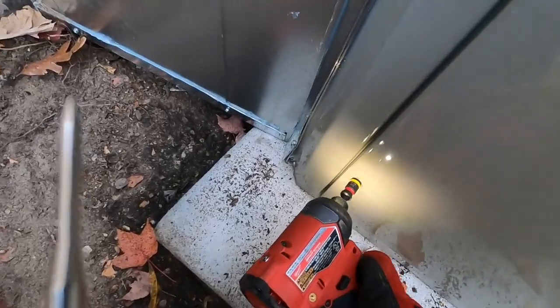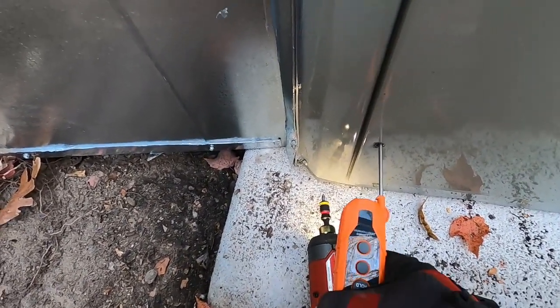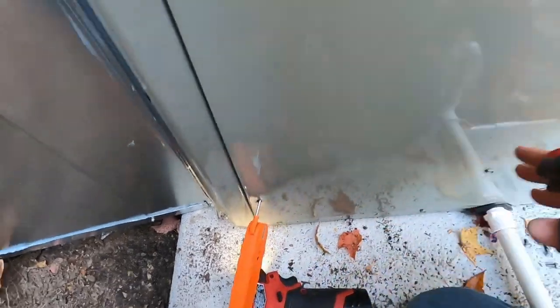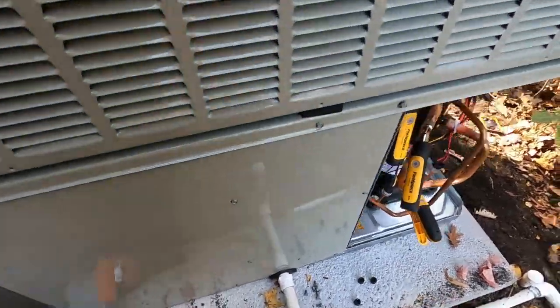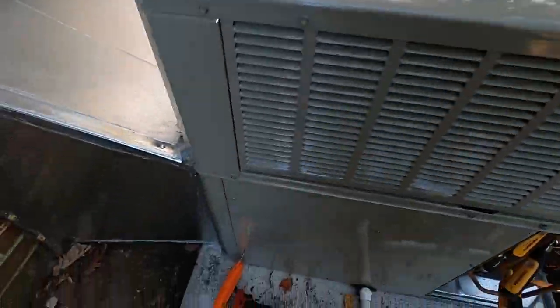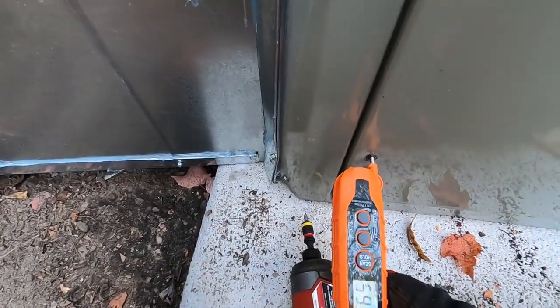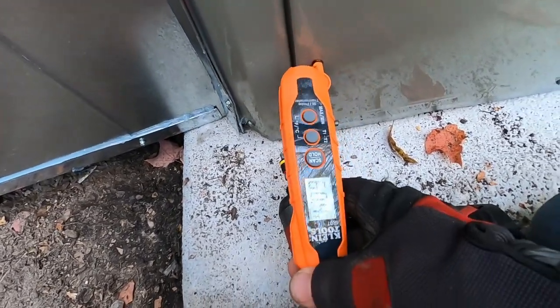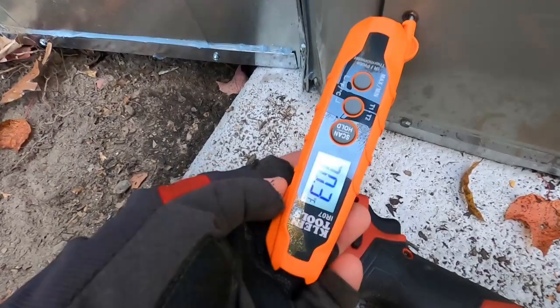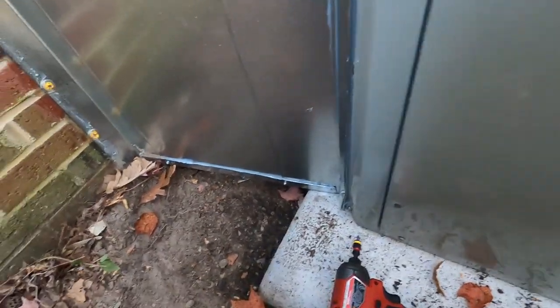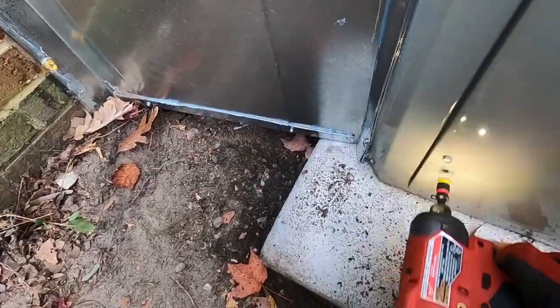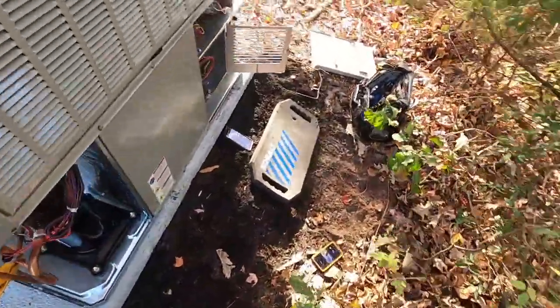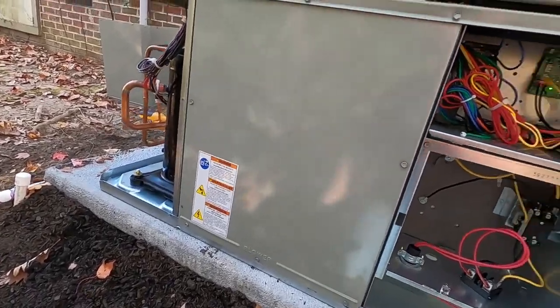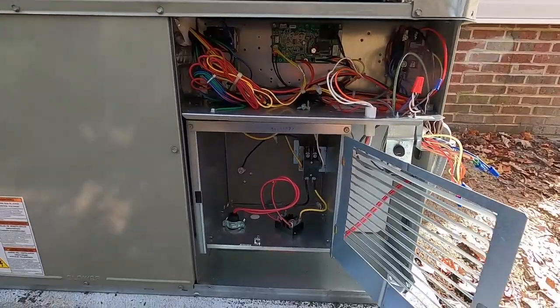Come around here. We'll get my return. This is now going to be the return side of the system. Pressure's right down there. So we're up to about a 68, 69 return. And then we'll go in there and switch the heat on. See what our refrigerant charge is looking like in heat mode, get our temperature rise, check our heat strips, make sure they're functioning properly.